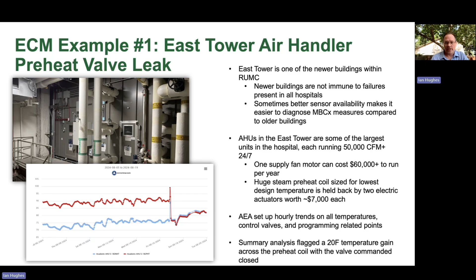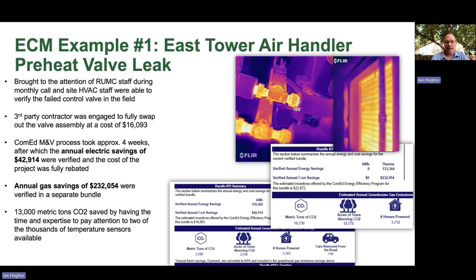We engaged a third-party contractor to swap out those valve assemblies. That cost about 16 grand. That money was paid back through the program itself. It took about 4 weeks total, and we have annual electric savings as a result of this valve swap of about $43,000. But the big kicker here was gas savings of nearly $232,000 that was verified annual savings, because we were just wasting natural gas as we were preheating those spaces with pre-made steam. So 13,000 metric tons of CO2 saved by having the time and expertise of these folks digging into this anomaly, finding and ground truthing it, and then making the appropriate fix.